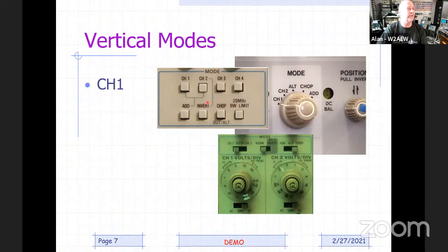In terms of vertical modes, depending on how many channels you have, channel 1 through channel 4, you can select one channel or the other. You can select Alt. What Alt does is, when the beam sweeps across, it first shows you channel 1, the next sweep shows channel 2, the next sweep shows channel 1, and it alternates back and forth. But oftentimes your sweep speeds are fast enough that you don't see this. You just see two live traces on the screen, and they're both there because the persistence of the phosphor leaves them on the screen. So it just looks like they're there.